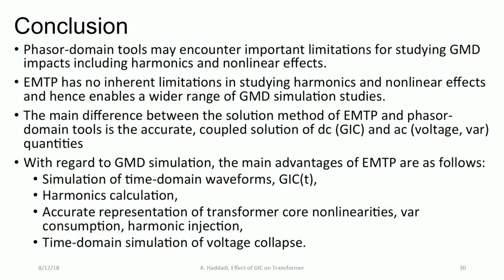In conclusion, phasor domain tools may encounter important limitations for studying GMD, especially regarding the impact of harmonics and nonlinear effects. In EMTP there are no inherent limitations — we can calculate harmonics accurately and model nonlinear effects. The main difference between EMTP and phasor domain is the accurate coupled solution of DC and AC quantities. The main advantages of EMTP are: time domain waveform simulation, harmonics calculation, accurate representation of iron core nonlinearities, VAR consumption modeling, and time domain simulation of voltage collapse.